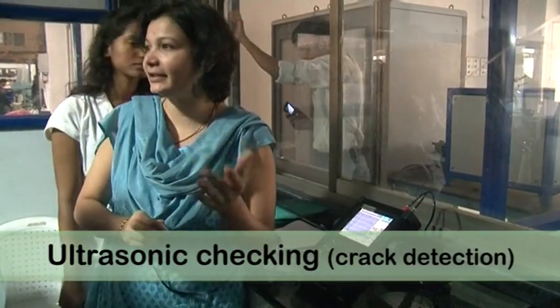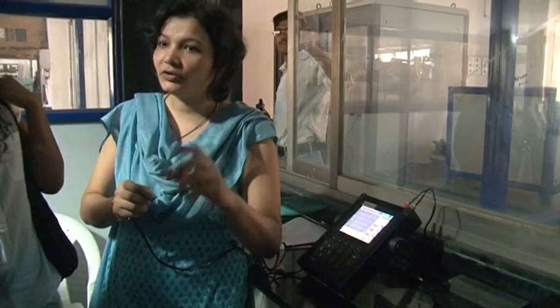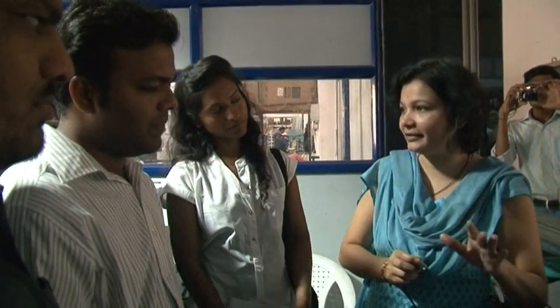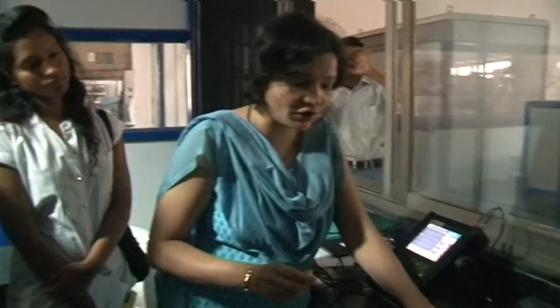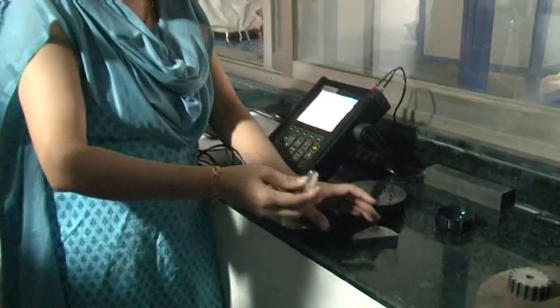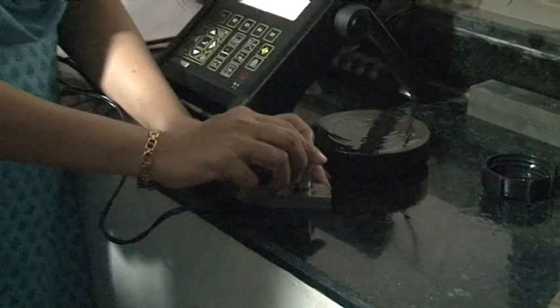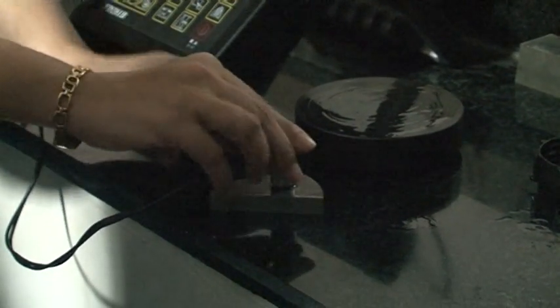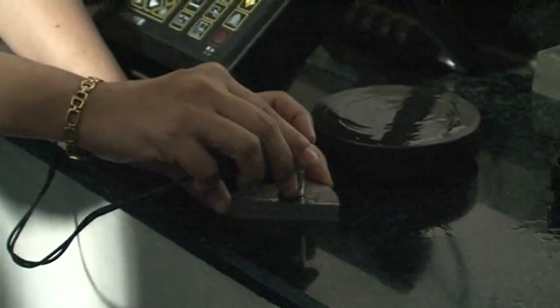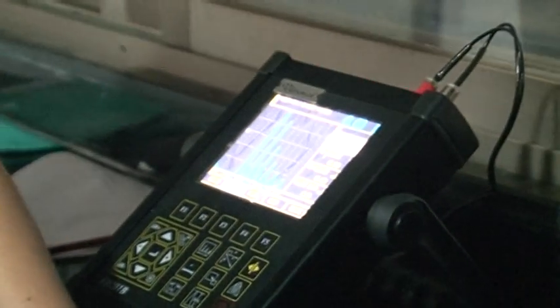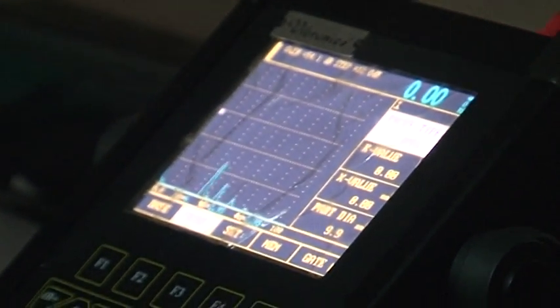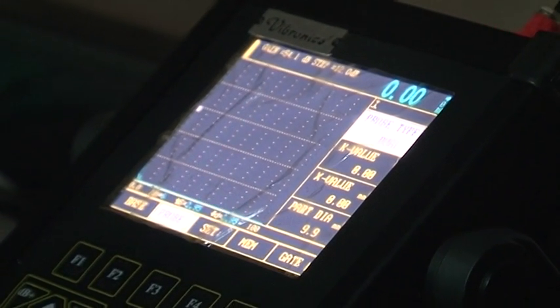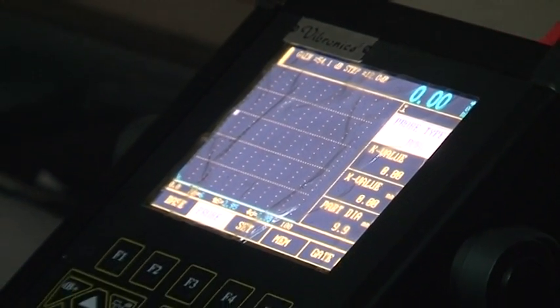Ultrasonic testers. As the name suggests, a very high frequency megahertz sound wave is used for testing internal defects. The material specification should allow the passage of sound wave. The machine has a megahertz sound generator which sends sound waves through the lab specimen. At the entry point, the graph will show a peak, and at the exit point the graph will show a peak. The entry and exit points are the edges of the specimen.